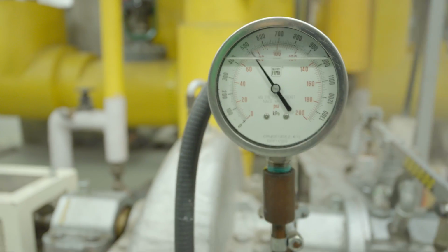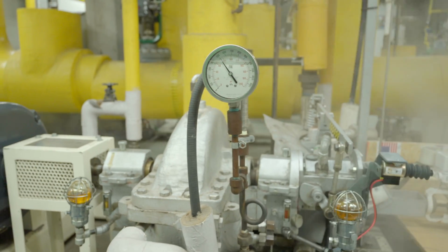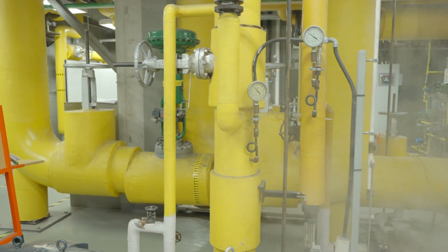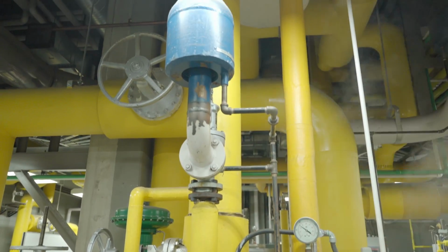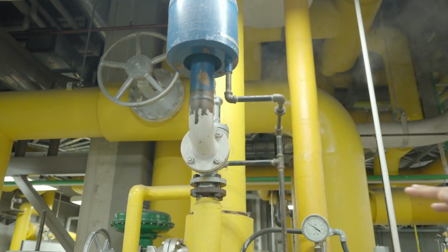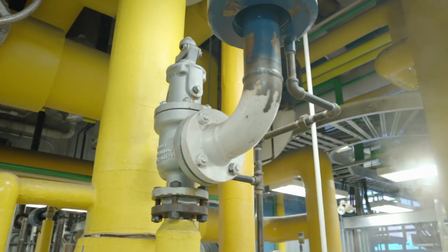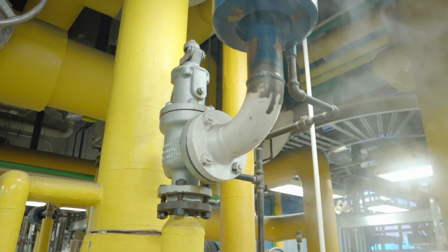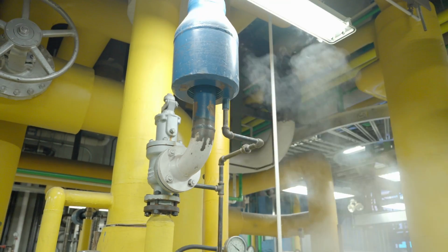Obviously, maintaining the pressure is important. We don't want to overpressure the components, which are only rated to a certain point. One of the other components we have on the low pressure header is our pressure safety valve on the back here. So in the event that we start pushing too much pressure into the low pressure header, and any of the systems aren't prepared to compensate for it quickly, that'll be the blow-off valve that releases to relieve some of the pressure so we don't cause any damage to the lines or to any of the fittings.